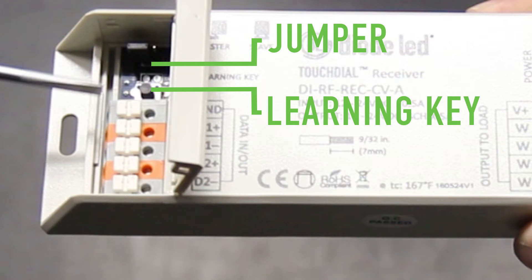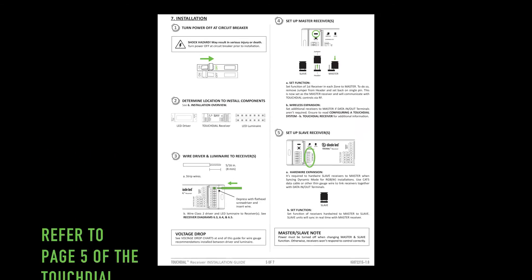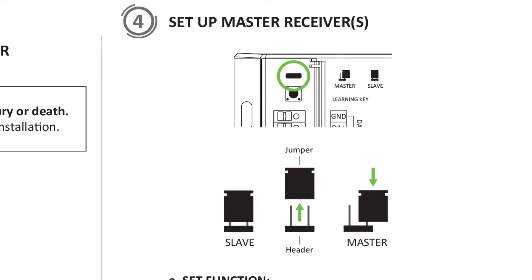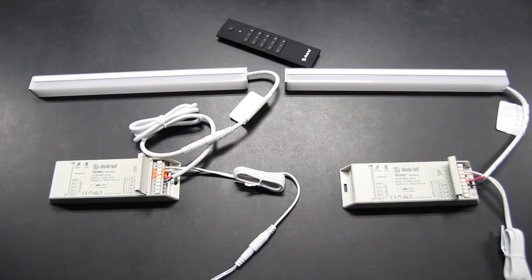Locate the jumper and learning key found on the left side of the TouchDial receiver. Confirm the jumper is sitting on one header pin. If it's not, move the jumper to a single header pin using your fingers or a set of needle nose pliers. Once those details have been confirmed, reconnect power to the TouchDial receiver.